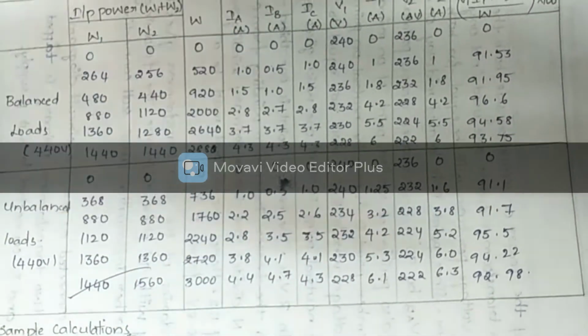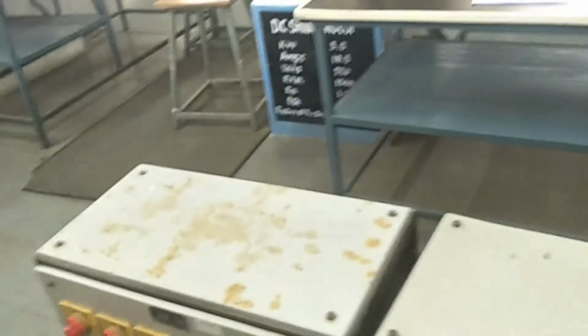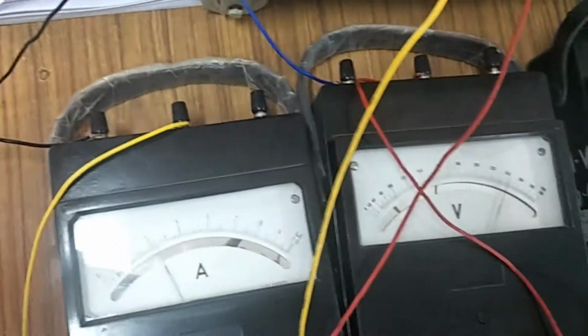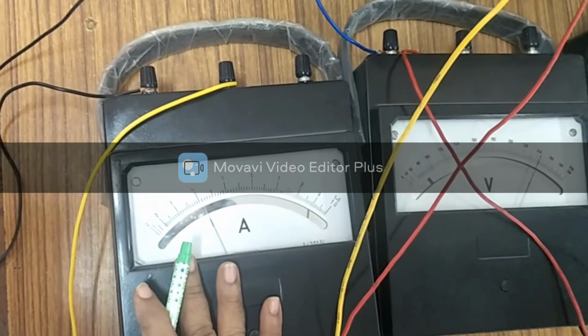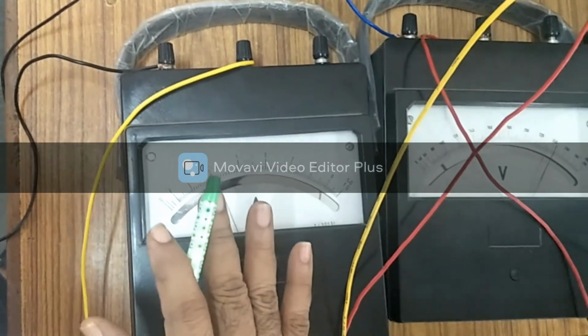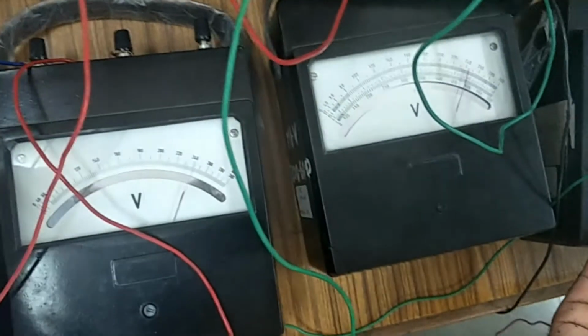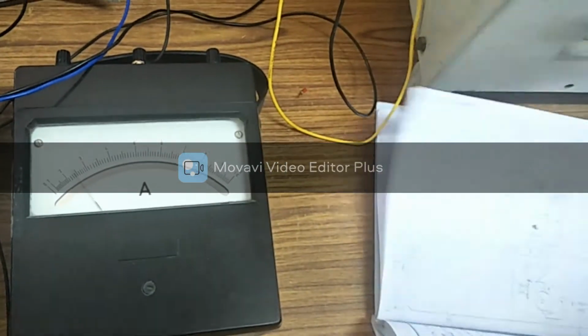Similarly, for unbalanced load, it's very simple. Turn on load 1 separately and load 2 separately. You have to see that the ammeters on the secondary sides of the two transformers read different values. That means the secondary side of the main transformer should read a value different to that of the secondary side of the teaser transformer. So like that you have to maintain two different readings, and then note down all the values of the transformer as shown here.